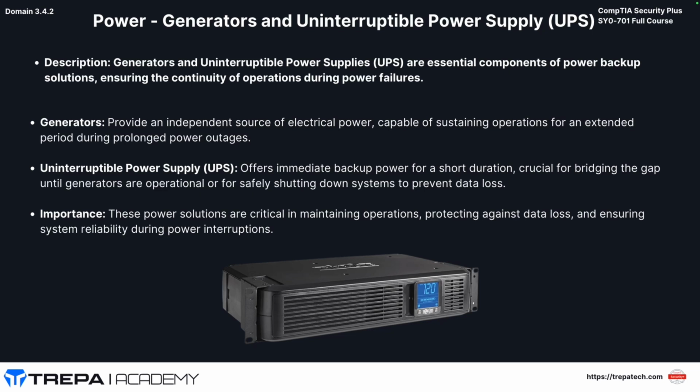Now, a UPS can also help you with rolling brownouts. Imagine you're in an area or a country, I've been in these countries before, where there's brownouts. Power goes down and comes back up, or we're not getting enough power. There's surges, or whatever the opposite of a surge is, where power gets lower, but you're still getting some power. That can mess up your systems, but it's not enough for a generator to take over because it's not a sustained blackout. You don't want the generator to come on and then a second later the power's back on and the generator goes off. You don't want that back and forth. Generators are for sustained blackouts. What a UPS can do is temporarily give you enough juice in the event of a brownout to keep systems online.